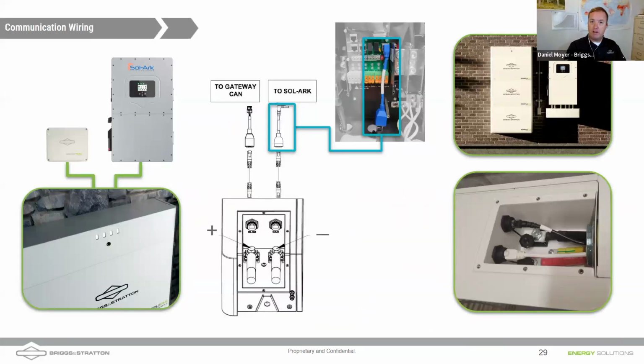All of these batteries in the market, even our 6.6 stacking battery, still have closed loop communications. We want the batteries and the inverters to be talking to each other. There's a lot of data that's transmitted on this closed loop CAN bus. For example, the battery is telling the inverter its state of charge, its temperature, and its physical capacities.